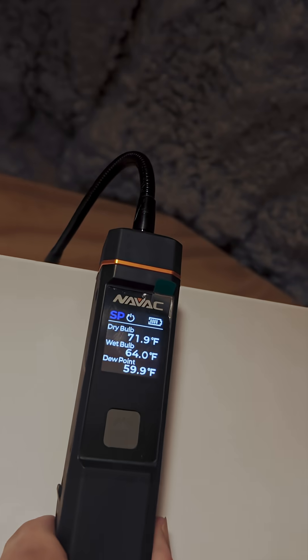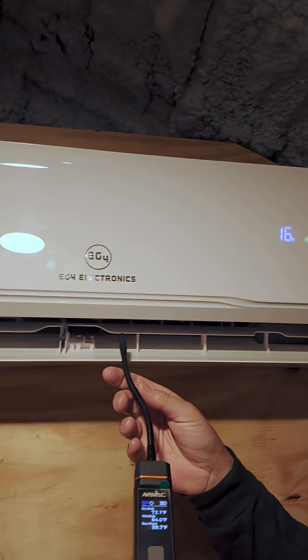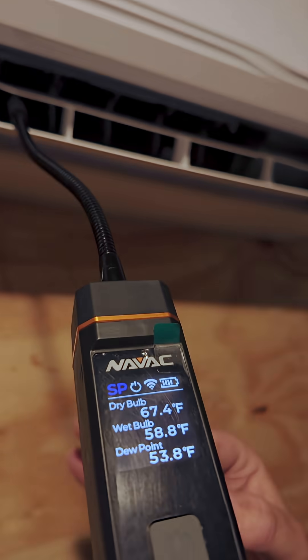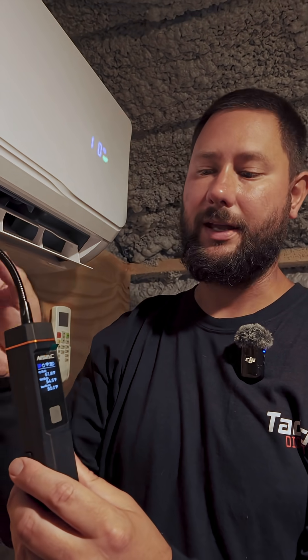Once we figure that out, we're going to measure the return air temperature. Once we get that reading — this one is 72 — we're going to subtract it from our supply air temperature. This is the air that's blowing out, and it should be about 20 degrees cooler than the air the mini split is pulling in.